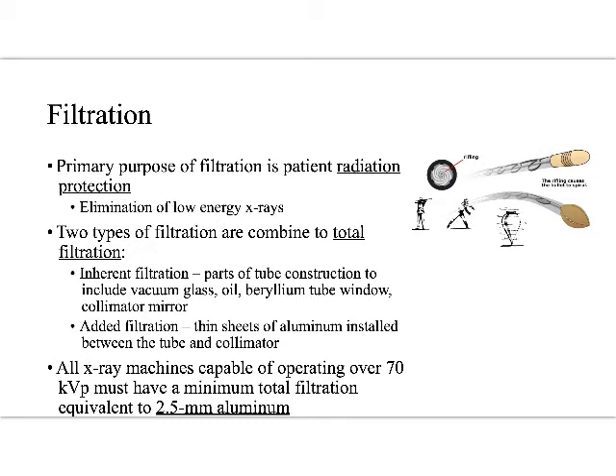We may need to add filtration beyond that. It literally looks like aluminum foil — just aluminum foil of exactly measured thickness and uniformity, used to filter out low-energy x-rays. It is generally placed between the collimator and the tube. Thin sheets of generally aluminum or aluminum equivalent are installed between the tube and the collimator. All x-ray machines operating at 70 kVp must have a minimum total filtration equivalent to 2.5 millimeters aluminum equivalent.